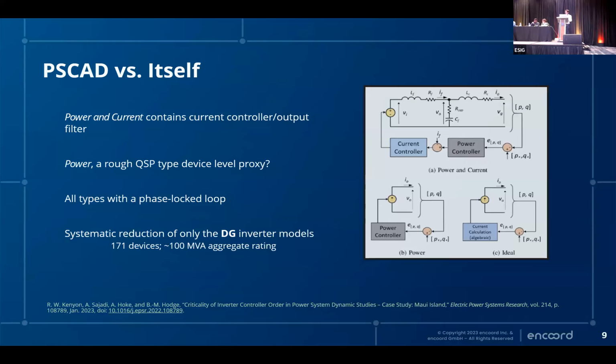Now it's easy to say PSCAD versus PSSE, but why not just make PSCAD versus itself? It's hard to compare two different commercially available software tools that are designed to do different things. They're not designed to do the same thing. That's inherent. So what we did is we looked at reducing the complexity of these generic inverter models. We said, well, we could take away the filter in the current controller and then just apply a current reference to PSCAD. You might end up with sort of a device-level QSP proxy in this case.